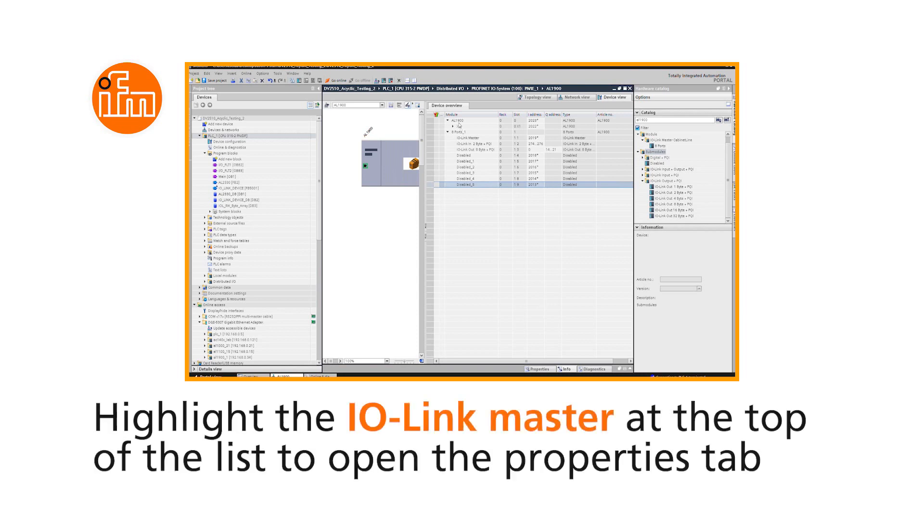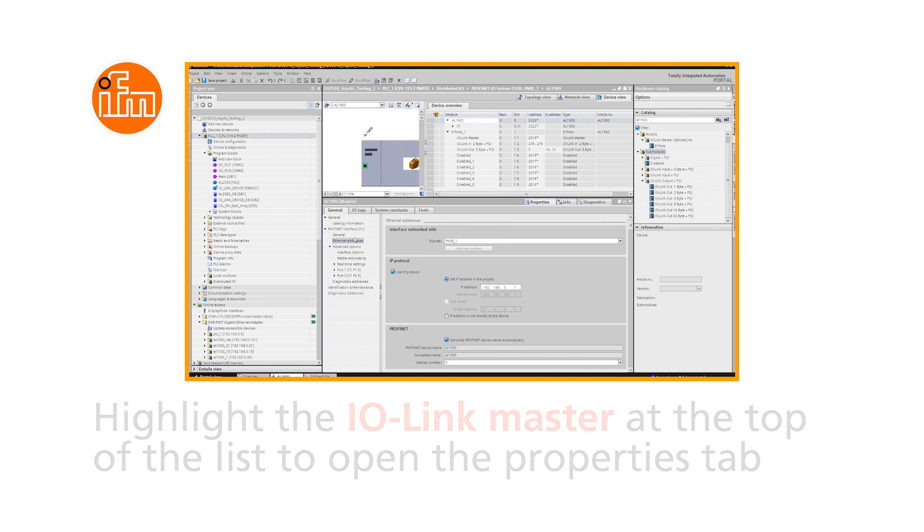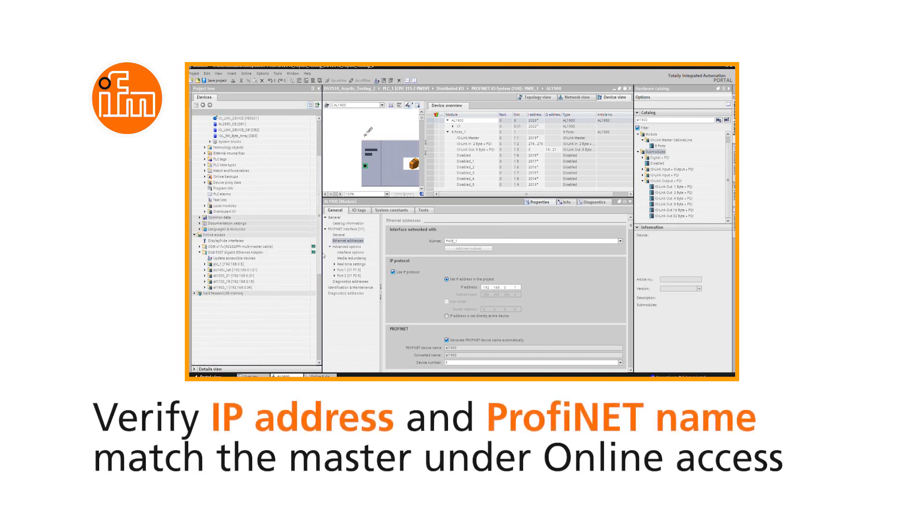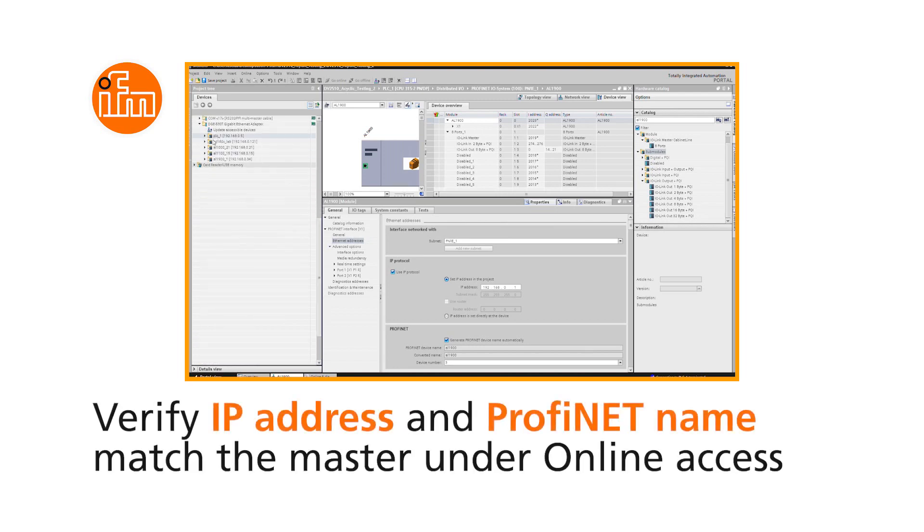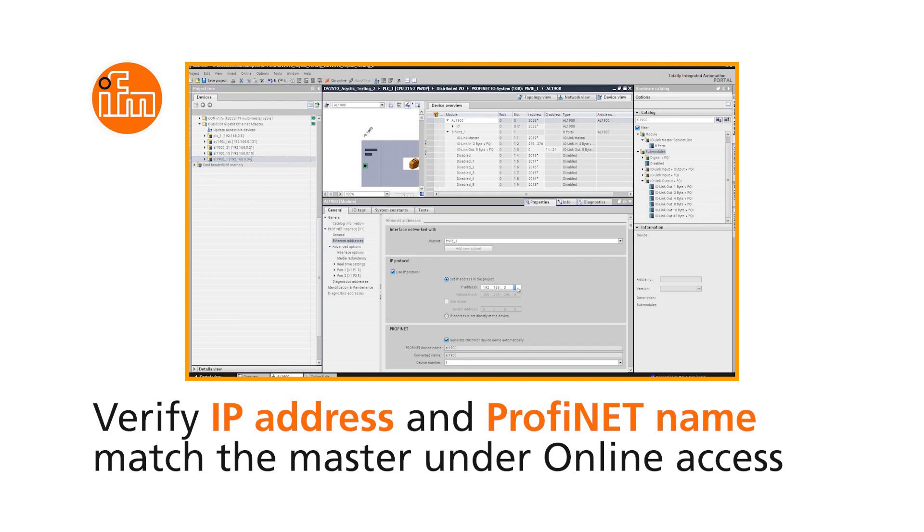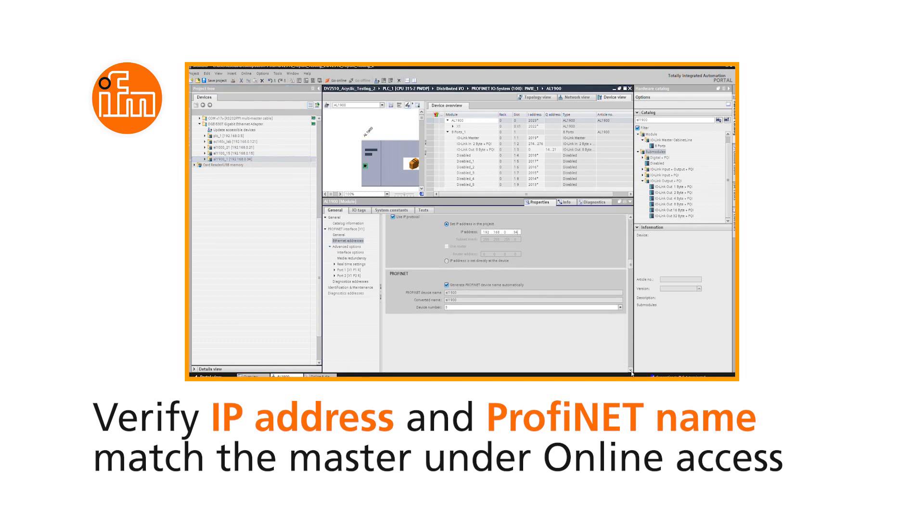Highlight the IO-Link Master at the top of the list to open the Properties tab. Under Ethernet Addresses, verify that the IP address and PROFINET name match that of the Master under the Online Access.